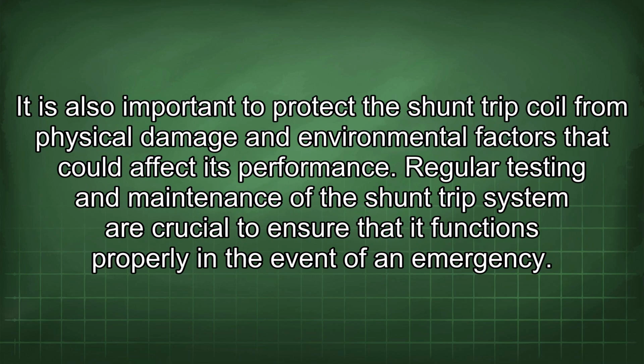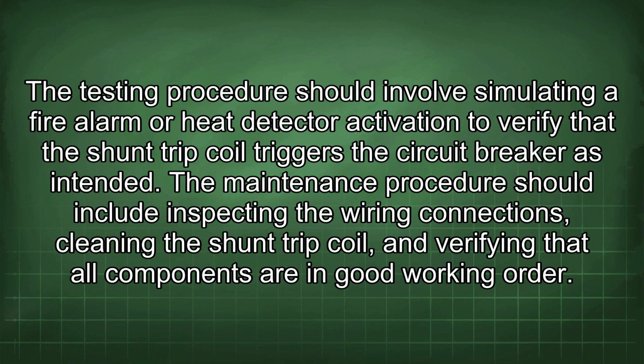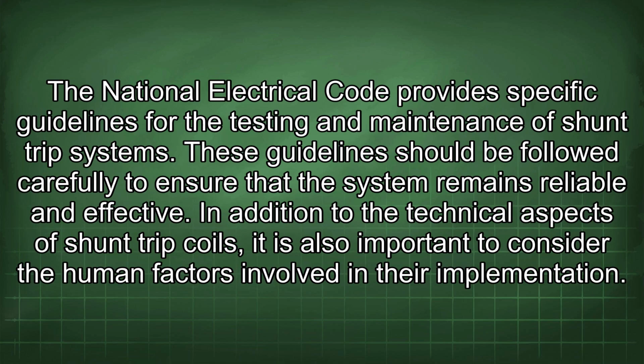It is also important to protect the shunt trip coil from physical damage and environmental factors that could affect its performance. Regular testing and maintenance of the shunt trip system are crucial to ensure that it functions properly in the event of an emergency. The testing procedure should involve simulating a fire alarm or heat detector activation to verify that the shunt trip coil triggers the circuit breaker as intended. The maintenance procedure should include inspecting the wiring connections, cleaning the shunt trip coil, and verifying that all components are in good working order. The National Electrical Code provides specific guidelines for the testing and maintenance of shunt trip systems. These guidelines should be followed carefully to ensure that the system remains reliable and effective.